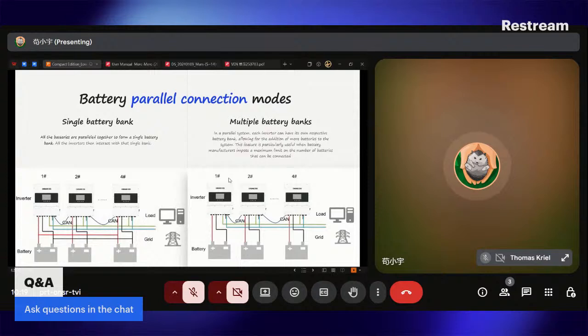Actually, we provide 2 ways to parallelize them. The first way is the traditional way. You connect all batteries to a bus bar and then connect them to each inverter. And the second way is, for some batteries you can only parallel 14 or maybe 16 batteries. That's limited by the manufacturer, but we can connect one battery to one inverter and then parallelize the inverters so that you can have 20 pieces of batteries in parallel.